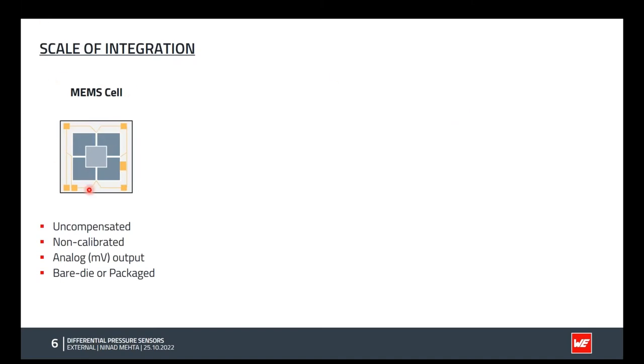Next, in my opinion, is one of the important slides to understand what the scale of integration is doing in terms of the pressure sensor. For example, what types of pressure sensors are available today in the market. The most basic ones are just the MEMS measurement cell, what we saw, only the bare silicon die, where you have the piezoresistors in a Wheatstone bridge and some measurement points to take the output. So this is the purely MEMS cell, which is purely analog. It is also not calibrated or temperature compensated. And this is available as a bare die or a packaged die, which you can use in your end applications.